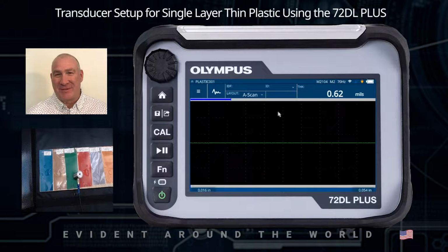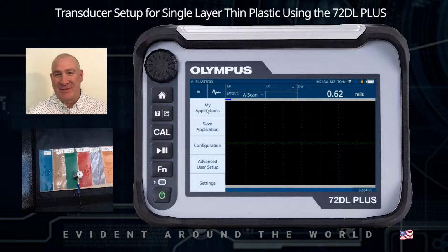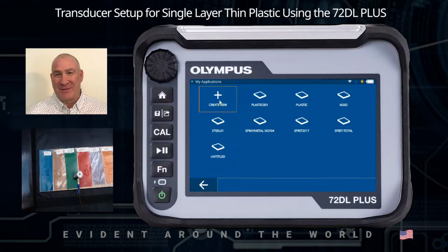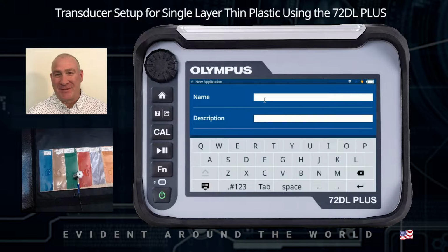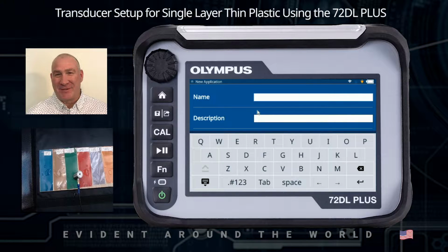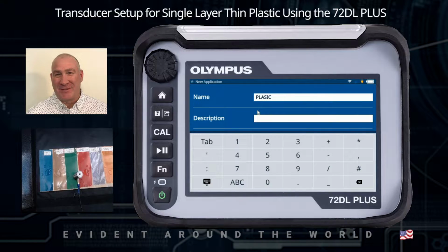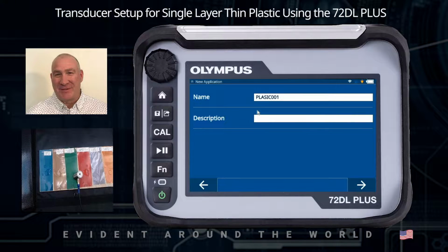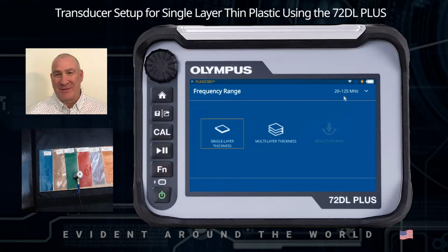Okay, so the first thing I want to do is click on the burger menu or touch the area and touch My Applications and select Create New. I can give it a name for the application. In this case here, I'm just going to type in plastic 001. I'm going to touch on the close keyboard and then click on the next arrow. So first, I want to select the transducer frequency. I want to make sure it's set to 20 to 125 because I'm using a 125 megahertz transducer. And then I want to select single layer.